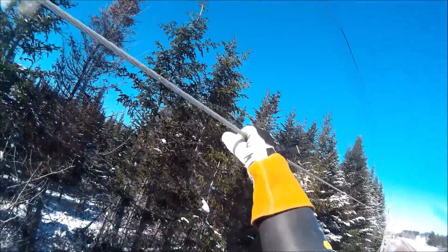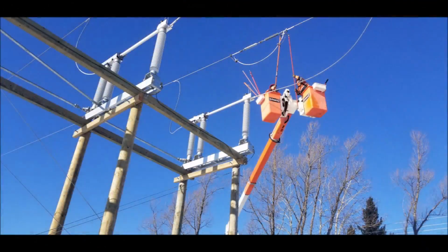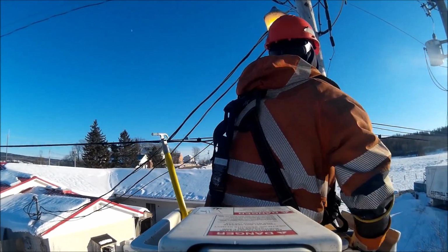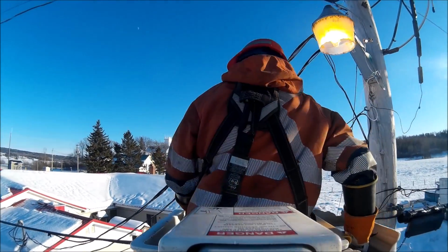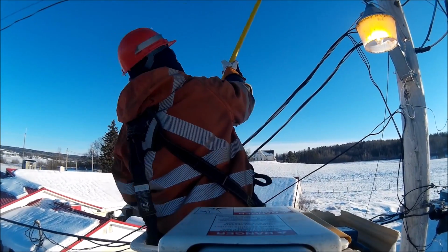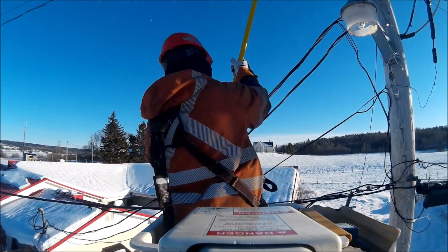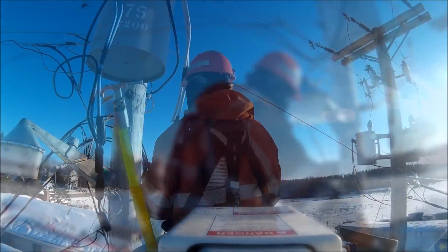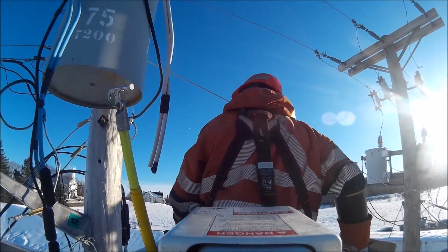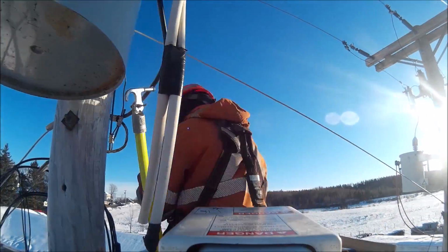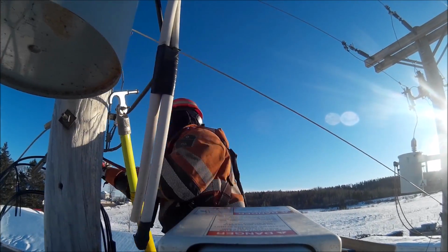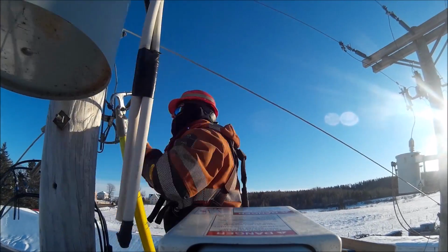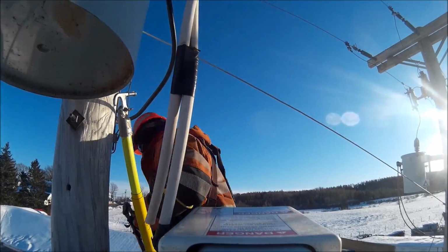As a journeyman lineman, you'll find yourself usually working on power lines while they are still energized, regardless of the voltage. Sometimes, however, we're lucky enough to open the line, or even the transformer. Problem is, this can easily lead to a false sense of security. Very important that you follow your company's work methods and procedures, especially when working on lines that have been isolated, as there are many ways in which the lines may still carry a lethal amount of voltage, even though such a danger may not be apparent.